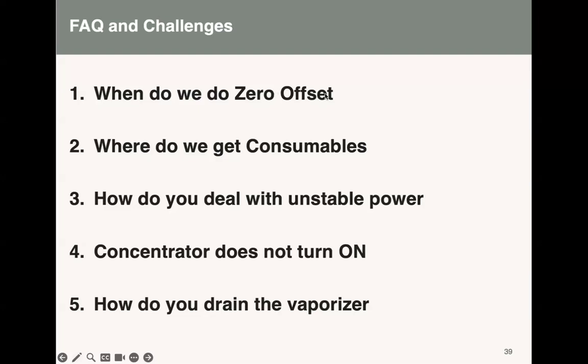Most of the time, when the concentrator is not turning on, you should also ask yourself, will there be an alarm or not? We all know that if there's a power challenge and the concentrator is not getting power, a certain alarm always comes. So most of the time it's a power challenge, and you can contact the biomed, or if you have someone on site, you can contact us. You can always contact someone who is always there to guide you.